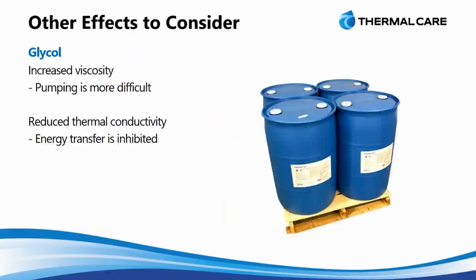So another aspect to consider that directly affects the performance of the chiller is if you're using glycol. Glycol is a substance that's mixed in a certain percentage with your process cooling water. Normally you could have 100% water, but if your set point is going to be lower and closer to freezing, you're going to want to have a mixture of glycol. Or if your chiller is going to be sitting outside, subjected to wintertime temperatures, you need glycol to protect from that. As you mix that in there, it becomes a more viscous fluid, so it's thicker. It goes from water to more like molasses, and so it's much more difficult to pump that fluid through the system. So your standard pump that you have in the chiller may not be able to achieve the desired flow rate of the system, so you need to be considerate of that, and the different percentages of glycol affect it accordingly. So those are things that you need to take into account.